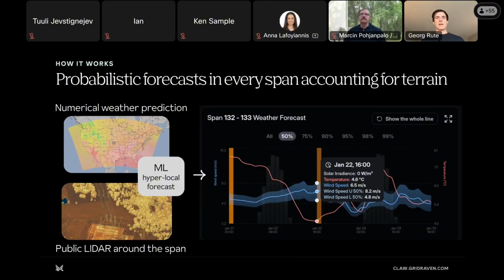This on the right is an example, and the key point is that it's probabilistic. We allow you to choose 50, 75, up to 99% confidence in the input variables for the line rating.